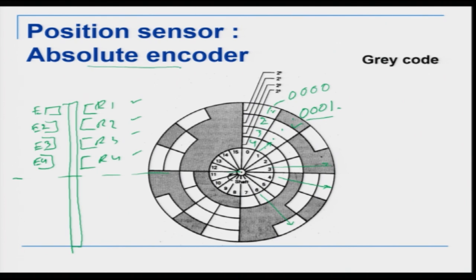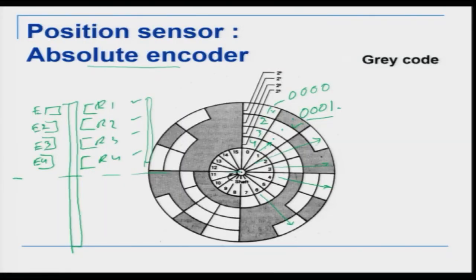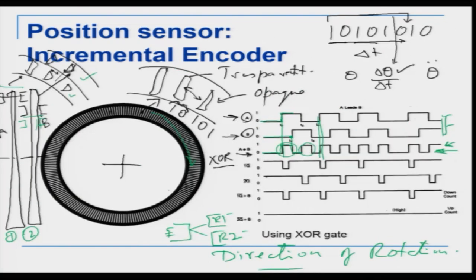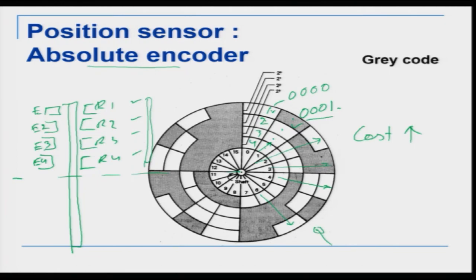The disadvantage is that now you have four rows of emitter-receiver pairs, plus you need logic circuits to determine exactly which sector it is on, so the cost of the system goes up. That's one reason it's not used as much. In about 99% of position measuring devices, the incremental encoder is used and is enough to give position, velocity, and acceleration. If you need absolute encoding, this absolute encoder is the option, though it's less used because cost and control system complexity go up.